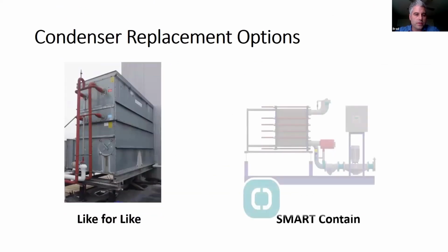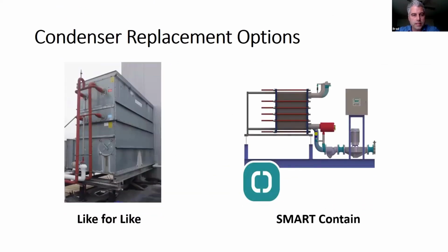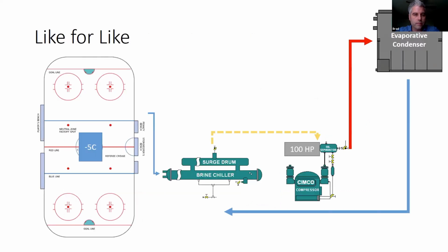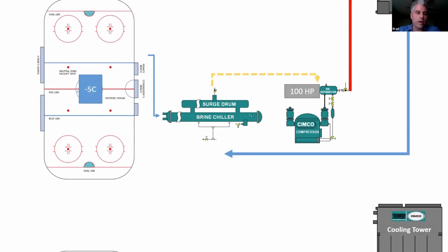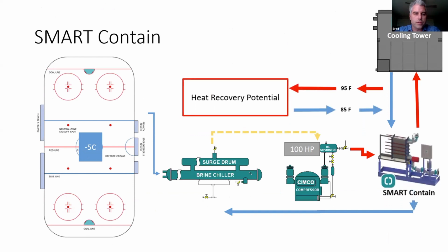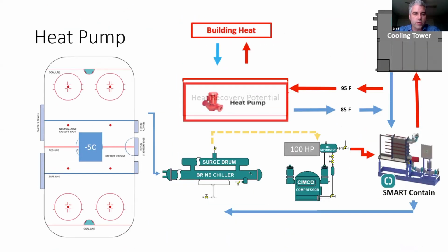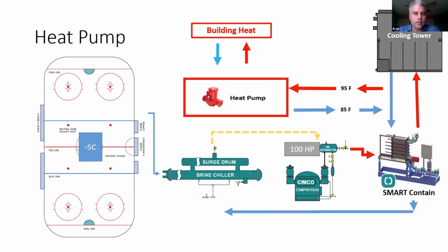Here are your condenser options: you can go like for like, or install a smart contain within the refrigeration room. The like for like option limits you, it doesn't provide any channel to recover that waste heat. Whereas the smart contain would be installed within the refrigeration room, giving you access to tie into that heat to preheat the building. One way is through a heat pump, sending all that free heat to different locations in the building and offsetting the natural gas required to run those HVAC units. The key is to ensure your controls are set up properly to recover the waste heat.